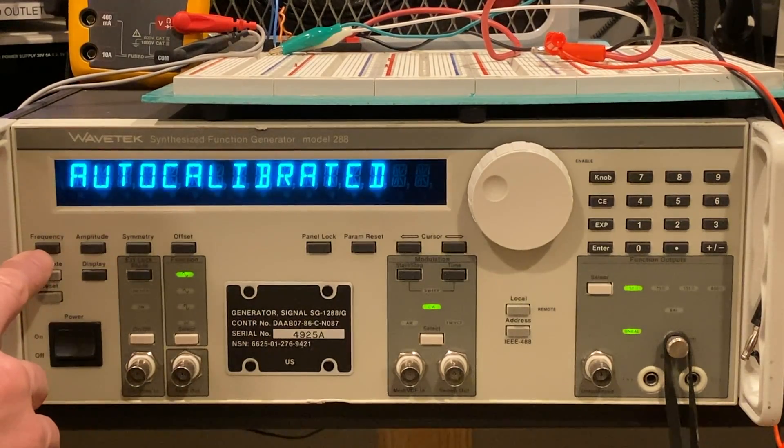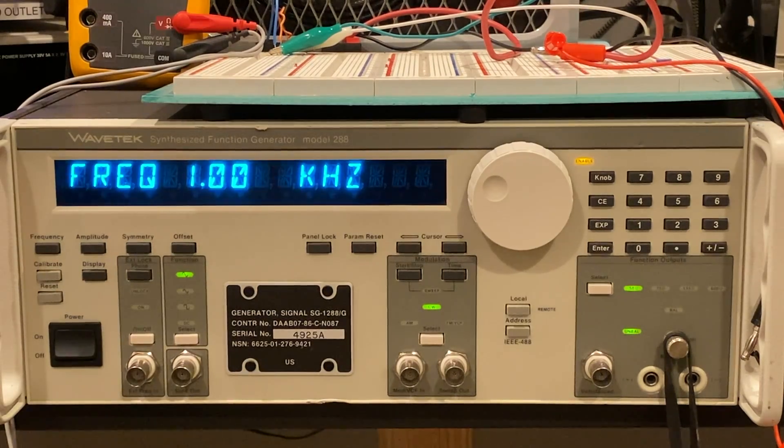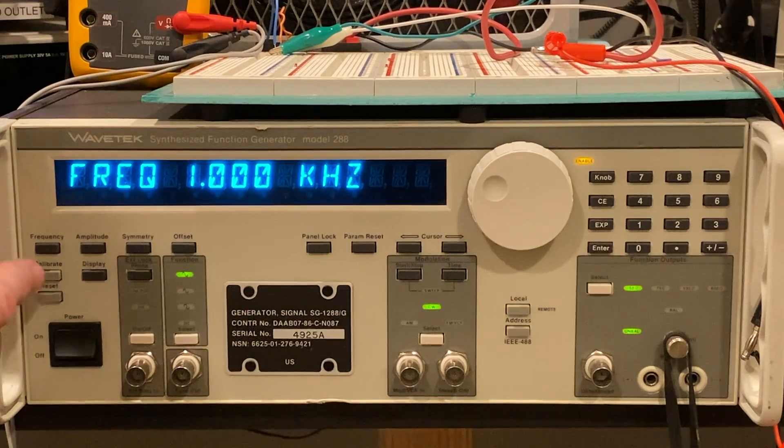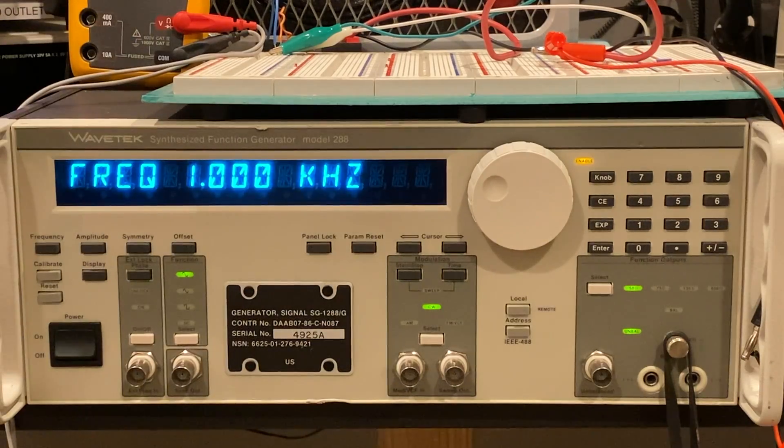Here we see the frequency button. If we press that we can see that the default is one kilohertz and that's from a RAM chip that we talked about in another video where the battery has to be replaced. That RAM chip stores a basic reset calibration and starting place for this particular unit. In this case the frequency they start with is one kilohertz, one millisecond per cycle.